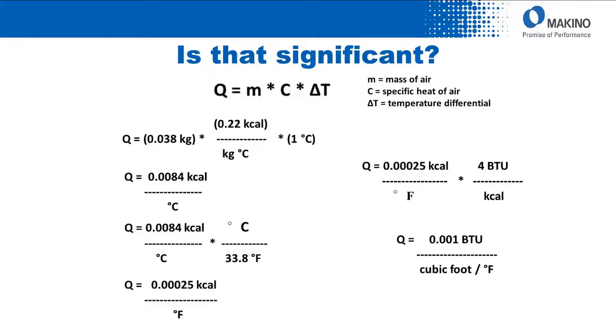So now what I can do is take that machine, the PS105, and build a little room around it. 12 by 12 by 9 feet tall, which happens to be 1,300 cubic feet. Now, how much heat's generated? Well, if I take that factor times 190,000 BTUs, that says I can change 190 degrees for every cubic foot of air I have.